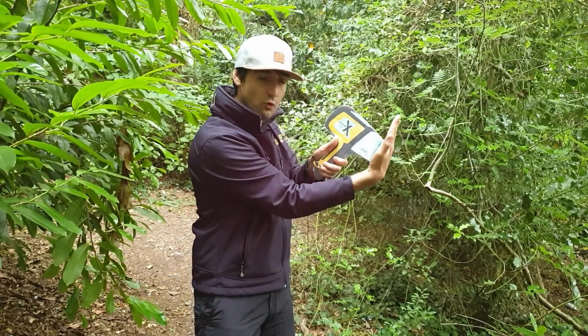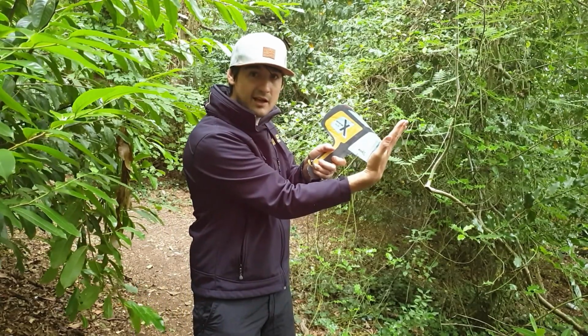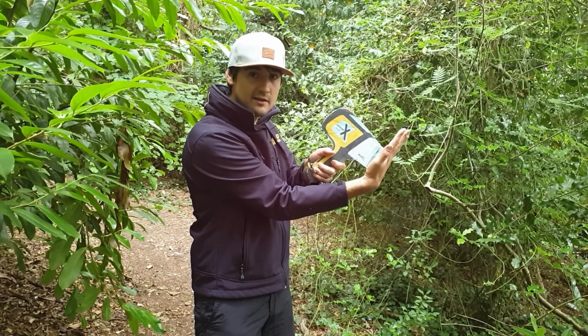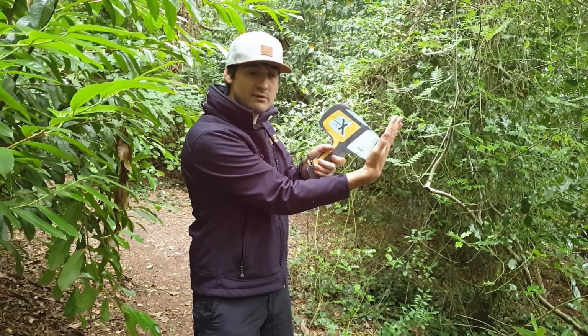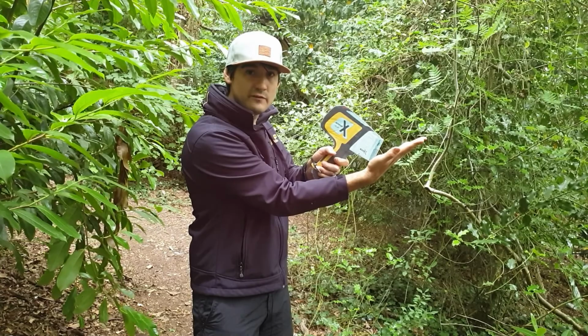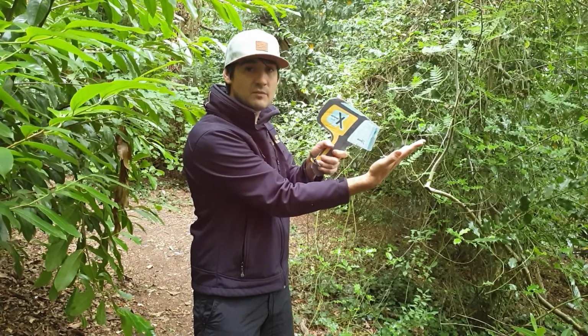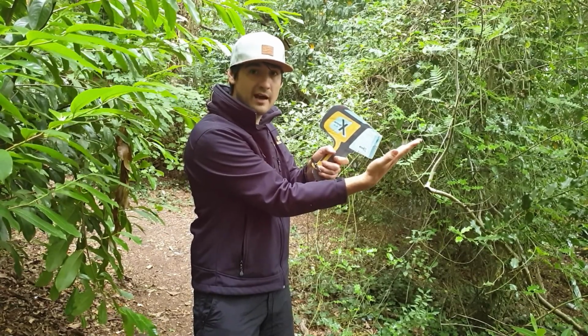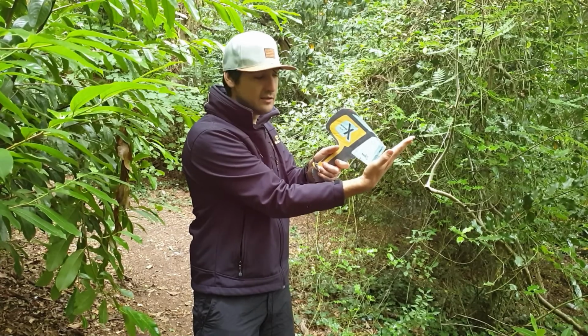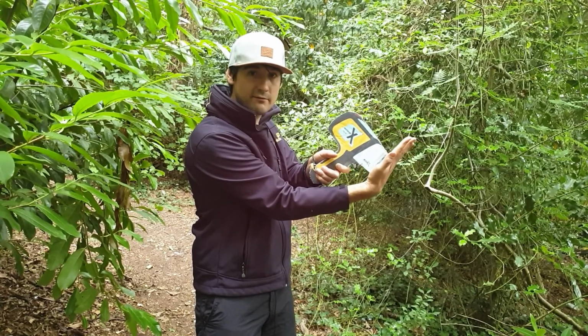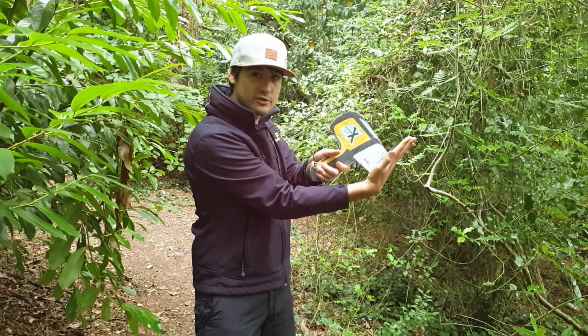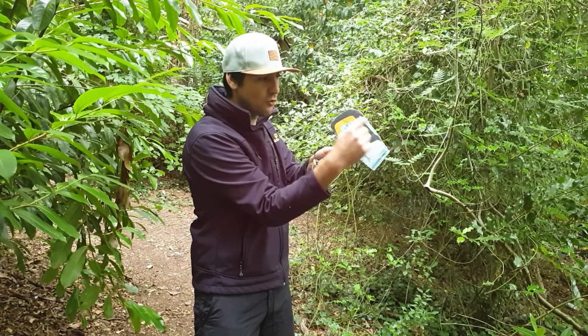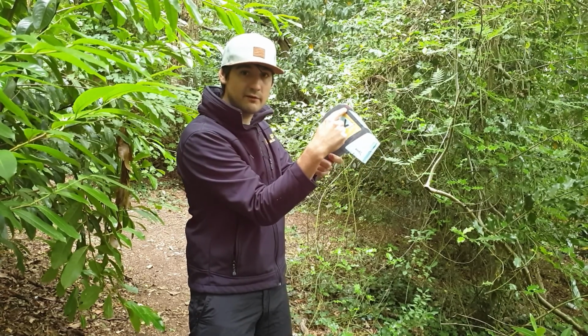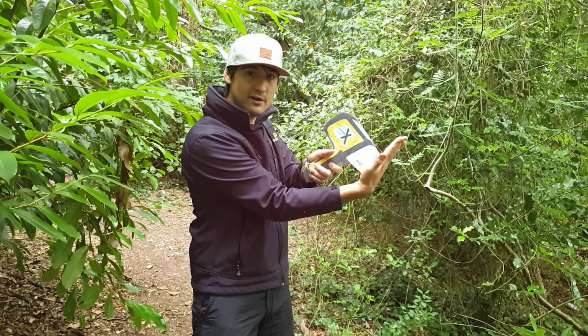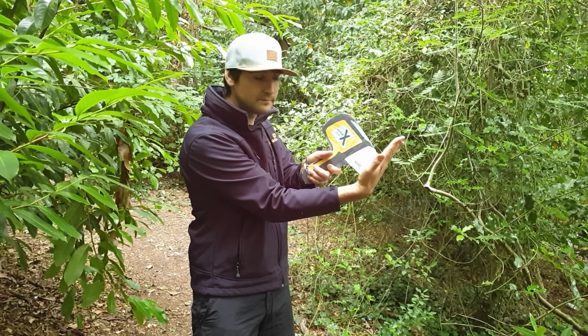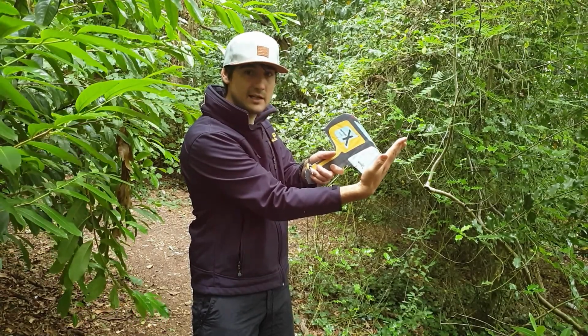It's very important to always keep the XRF flat against the surface that you're analyzing. The XRF has a built-in safety feature that if the XRF moves away from the analytical surface, it'll automatically switch off and create a failed reading. So keep that surface nice and flat, and for the duration of your analysis, so all the time the lights on the back of the XRF are flashing, the XRF needs to be flush against the surface that you're analyzing. So keep it nice and steady.